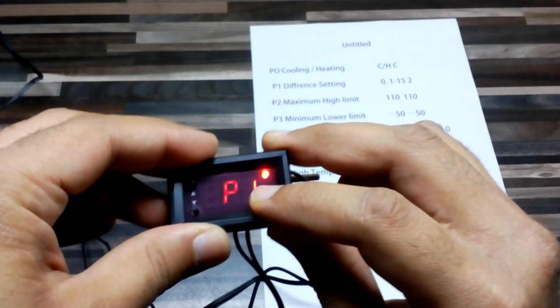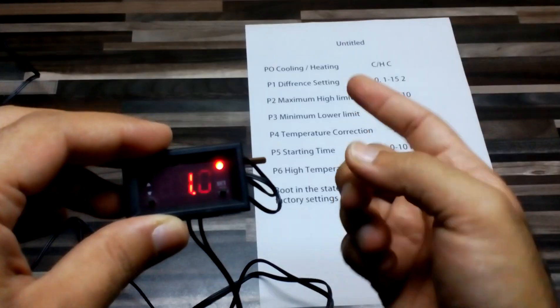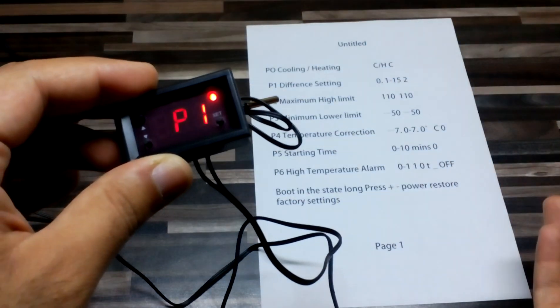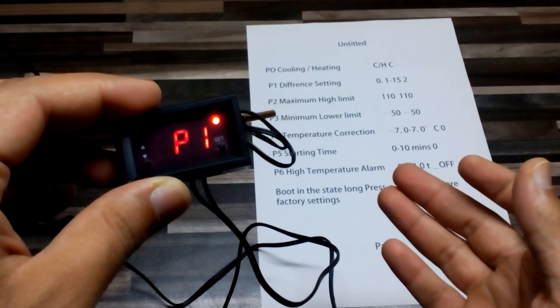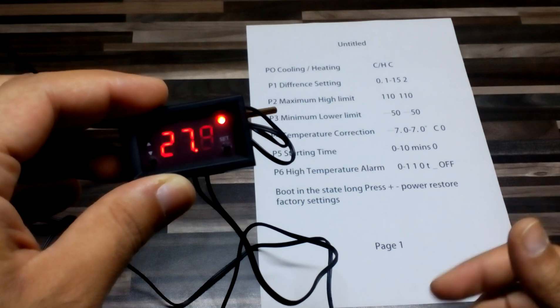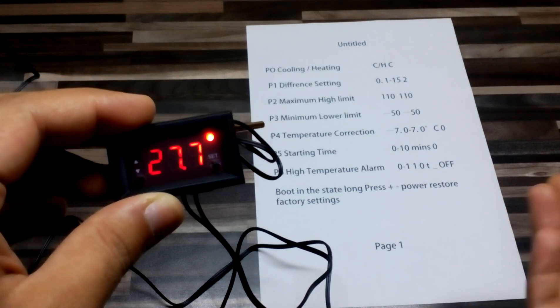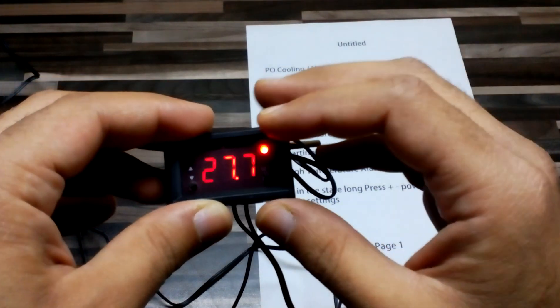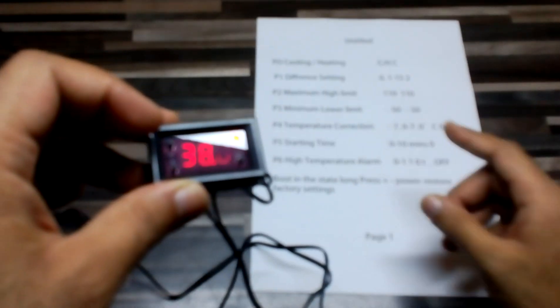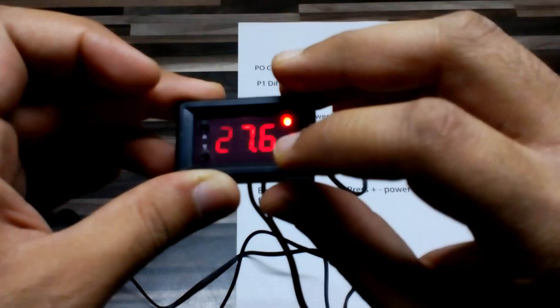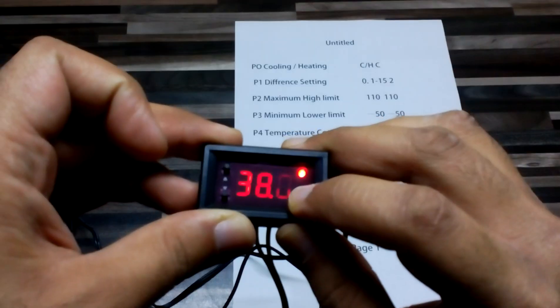On P1, you can set the difference setting. For example, if I want 38 to 37, it will be one degree difference, or if you want 35 to 38, it will be three degrees difference. We can choose from 0.1 to 15 Celsius.